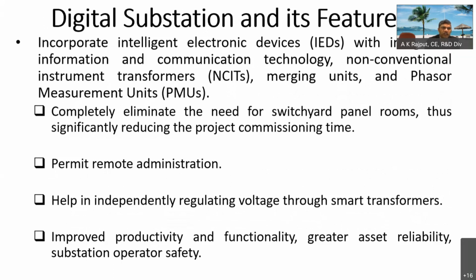Then in this series come the digital substations and their features. Digital substations incorporate intelligent electronic devices, that is IEDs. It is basically a higher form of relays and all those things combined into one integrated unit, which is communicable also. Of course, with integrated information and communication technology, non-conventional instrument transformers like optical CTs and optical PTs, which do not suffer so much damage and are not affected by electrical surges. Those units provide better measurement and metering parameters, merging units, and also phasor measurement units. Phasor measurement units also measure the phase.